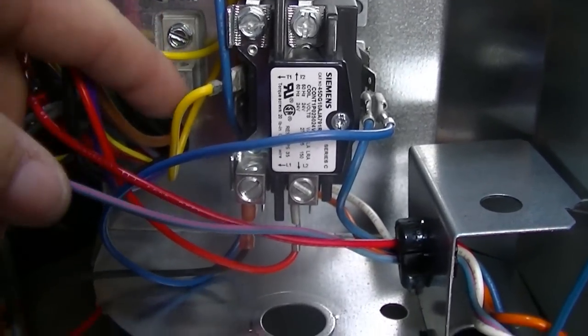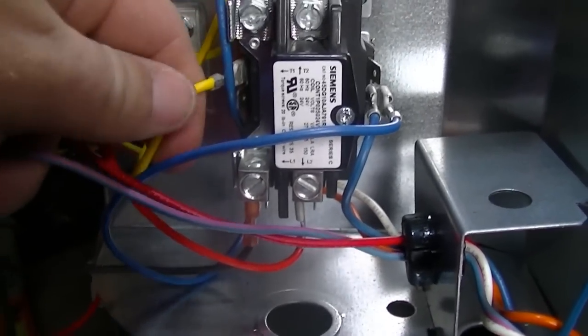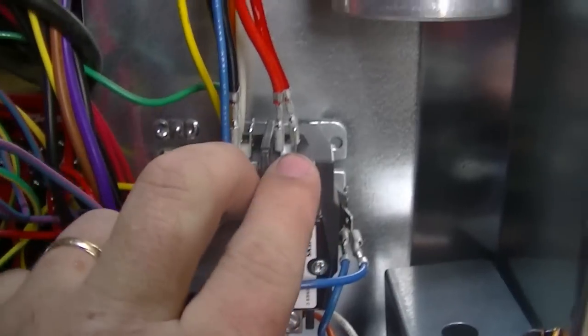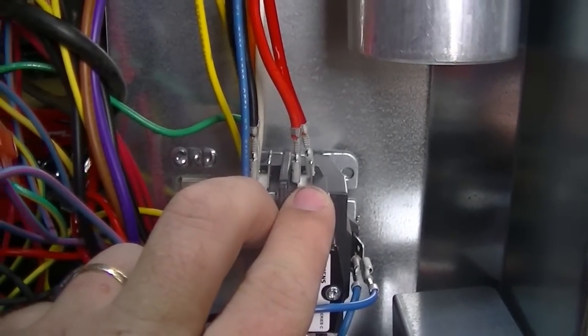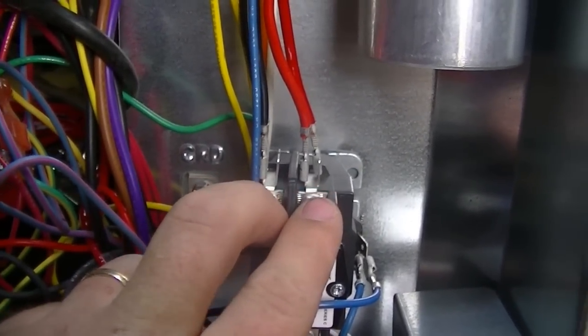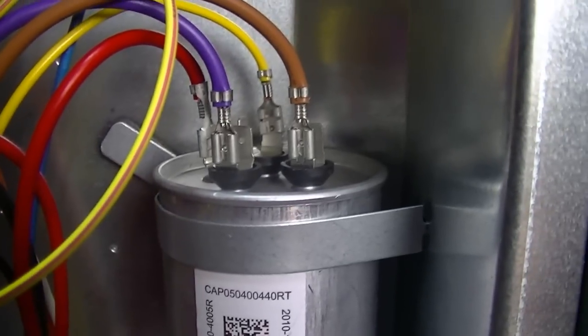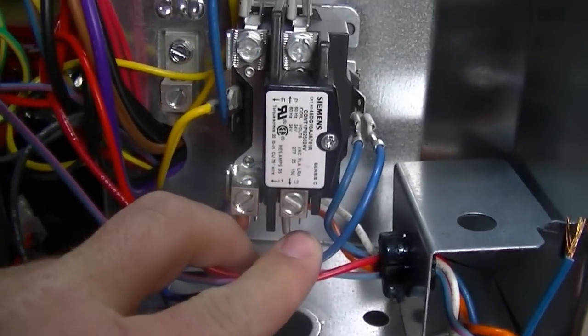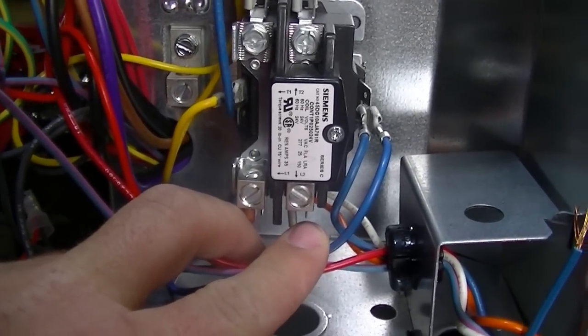If those switches say everything's all right, basically they're closed, it'll make it down here, energize the contactor, send power to the outdoor fan motor and the compressor. And as long as the components are good and the dual run capacitor is good, they will start. And that is the single pole contactor. Pretty common.